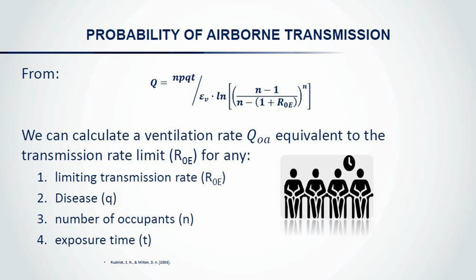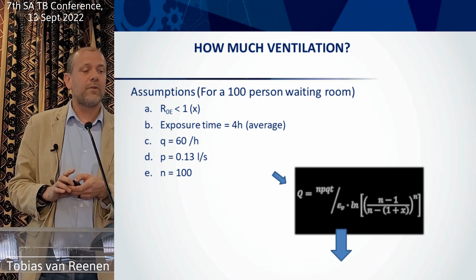Let's use that as an example to figure out how much ventilation we need for a waiting room. A 100-person waiting room is a reasonable size, quite big. Using all the values we've got for laryngeal TB, adults, 100 adults in the room, plugging that through the equation, we come out with a ventilation rate required of 3,200 liters per second. That is a lot of air.